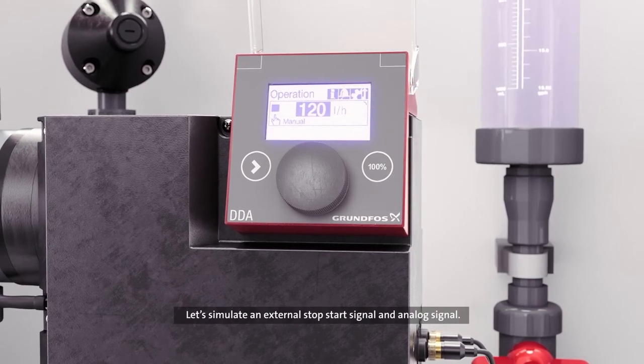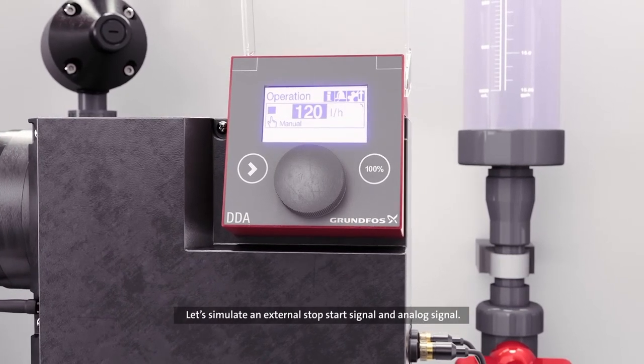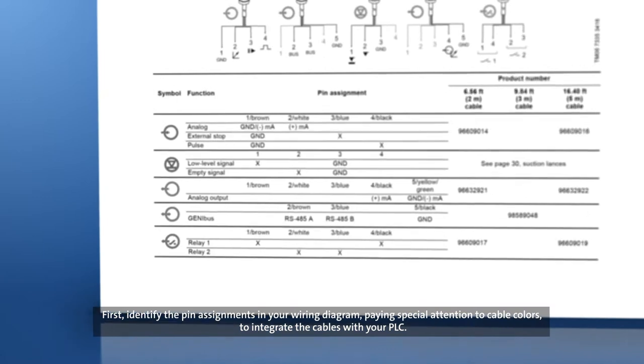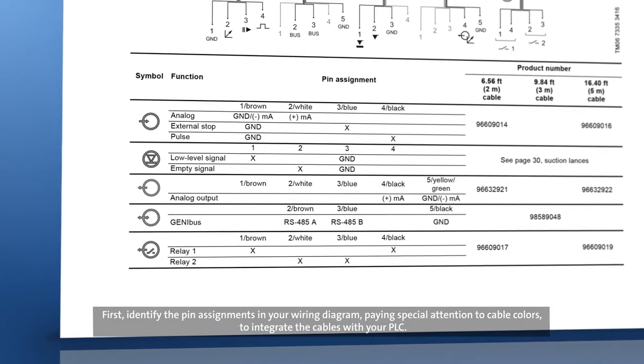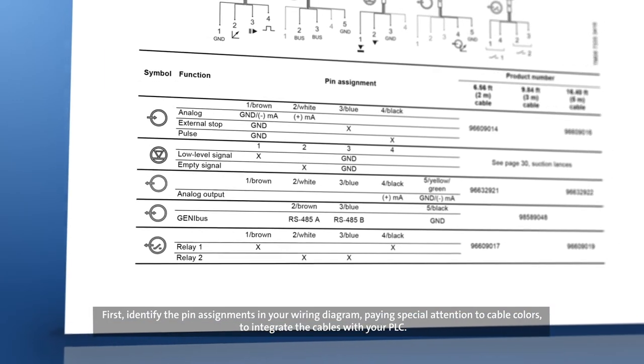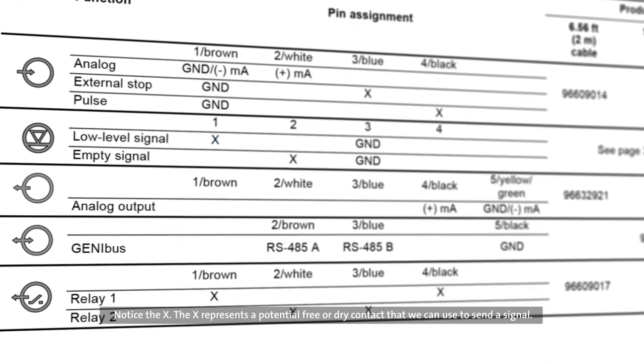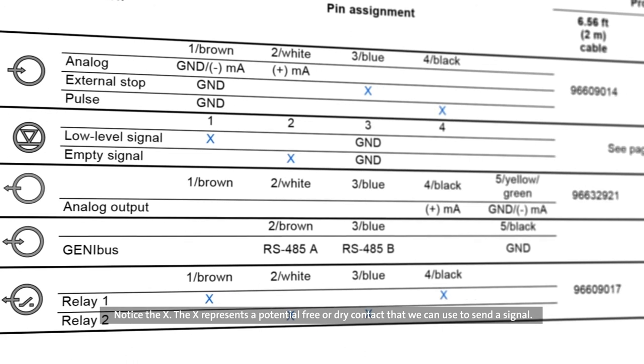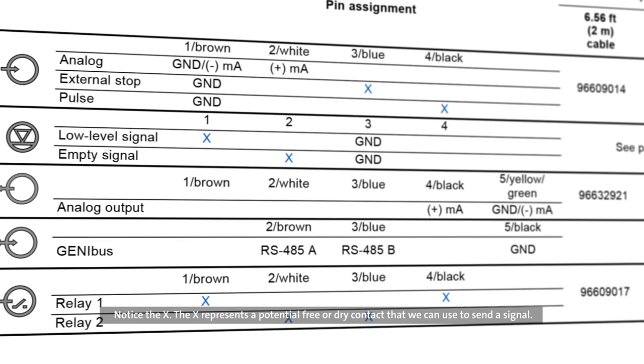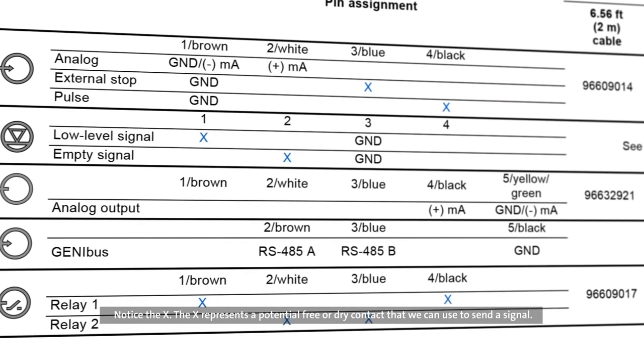Let's simulate an external stop start signal and analog signal. First, identify the pin assignments in your wiring diagram, paying special attention to cable colors, to integrate the cables with your PLC. Notice the X. The X represents a potential free or dry contact that we can use to send a signal.